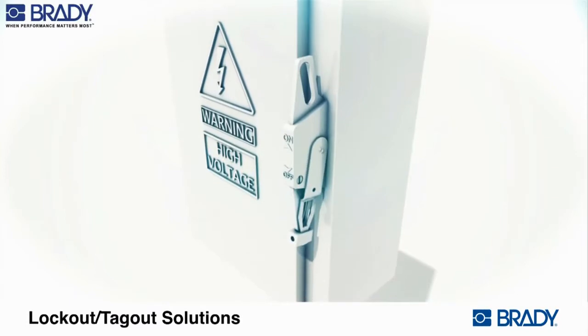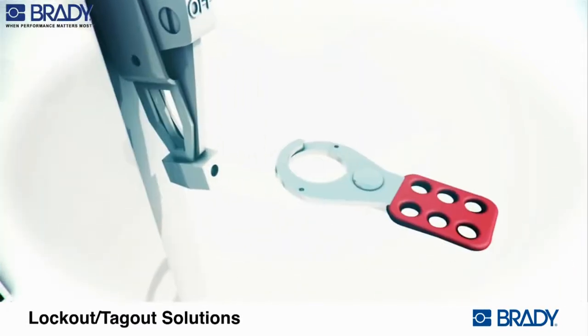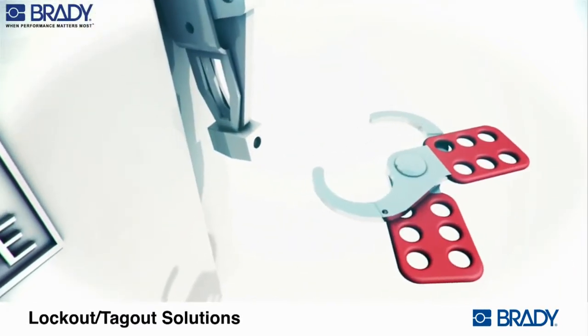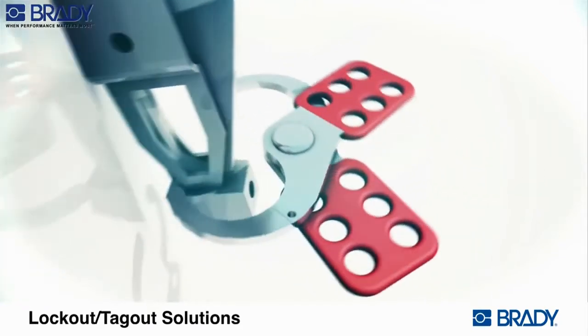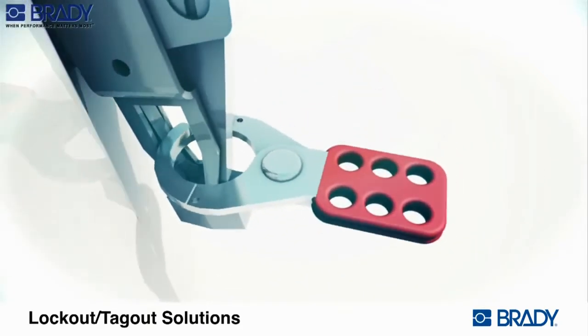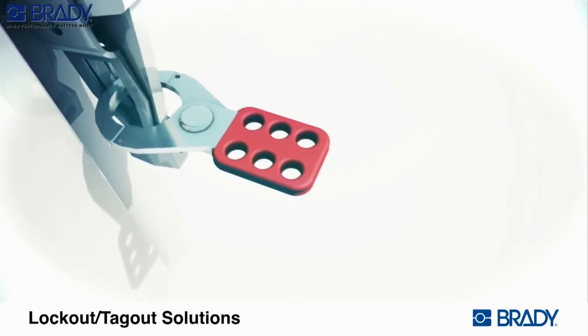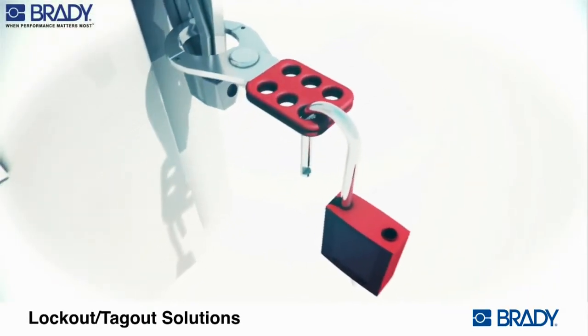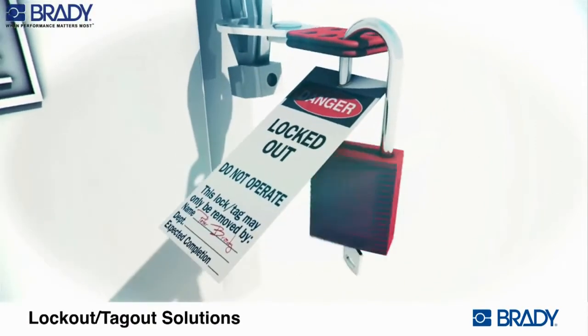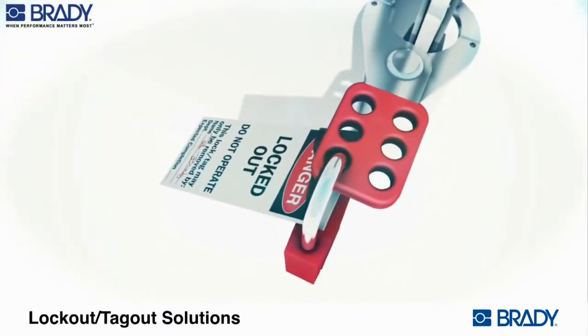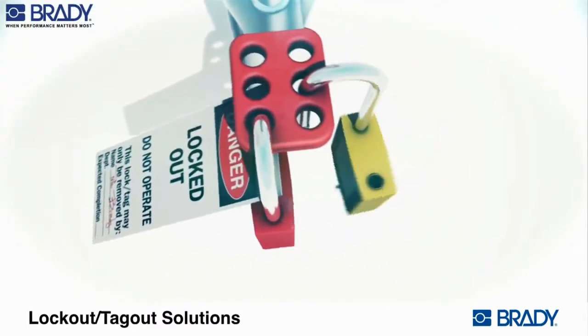Place electrical panel in off position. Separate and slide hasp ends in opposite directions to open device. Clasp lockout device on panel switch. Push steel hasps together to secure lockout device. Insert the padlock with worker's tag. Safety hasps are essential for group lockout scenarios and can accommodate up to 6 workers' padlocks for one device.